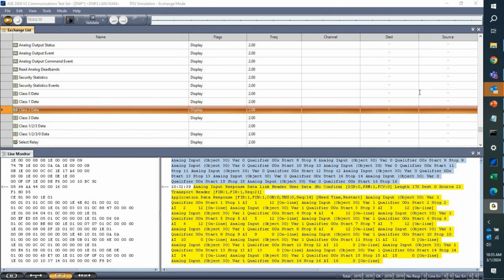So it's actually file size limited. It's not limited by a number of points. On an RTU with a larger configuration of point types and points, the return messages would be a much more sizable payload than, say, a level 1 outstation, which is just measuring select few inputs. So it's going to vary.